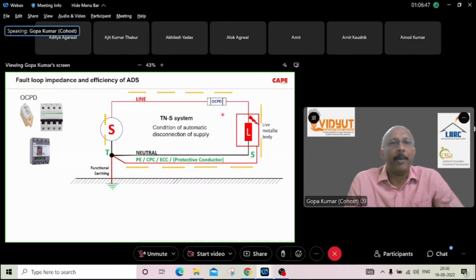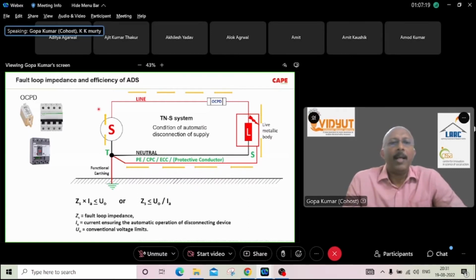Say, for example, you have a 10 amps MCB which is connected to a 1-ton air conditioner. The air conditioner is faulty. Within 0.2 seconds, the MCB should trip. For a 10 amps type C MCB, there are 3 categories of MCB, it requires a minimum of 100 amps current to trip within 0.2 seconds. Now the 100 amps current is decided by the impedance of this particular circuit, simple Ohm's law. And these calculations are written in the standard.